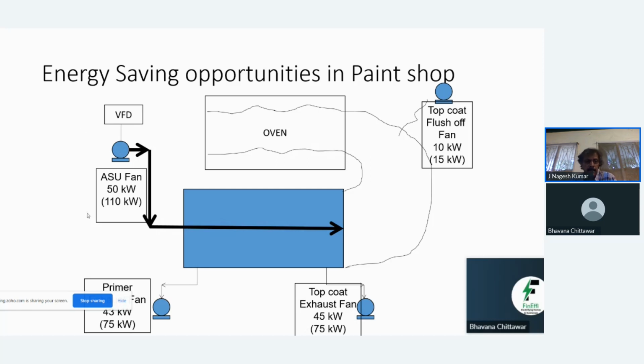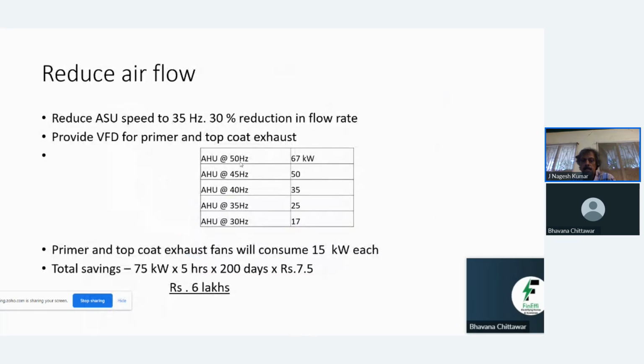So this fan, what is the optimum speed at which it should operate? Is this the optimum speed? That's a question. Then we operate this fan at different speeds. Say at 50 hertz, it is 67 kilowatt. At 45 hertz, it is 50 kilowatt. At 40 hertz, 35. So it keeps on coming down.